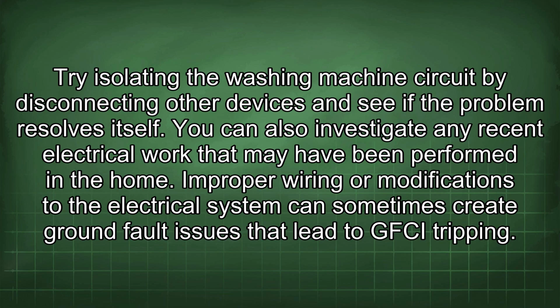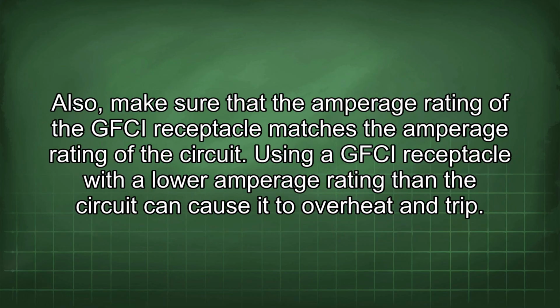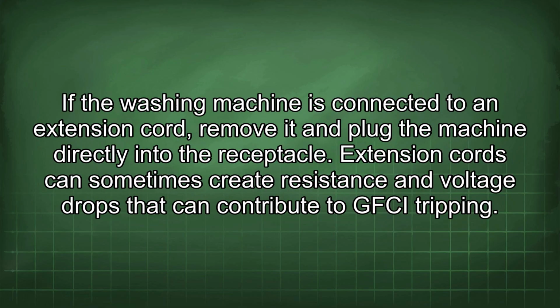You can also investigate any recent electrical work that may have been performed in the home. Improper wiring or modifications to the electrical system can sometimes create ground fault issues that lead to GFCI tripping. Also, make sure that the amperage rating of the GFCI receptacle matches the amperage rating of the circuit. Using a GFCI receptacle with a lower amperage rating than the circuit can cause it to overheat and trip. If the washing machine is connected to an extension cord, remove it and plug the machine directly into the receptacle. Extension cords can sometimes create resistance and voltage drops that can contribute to GFCI tripping.